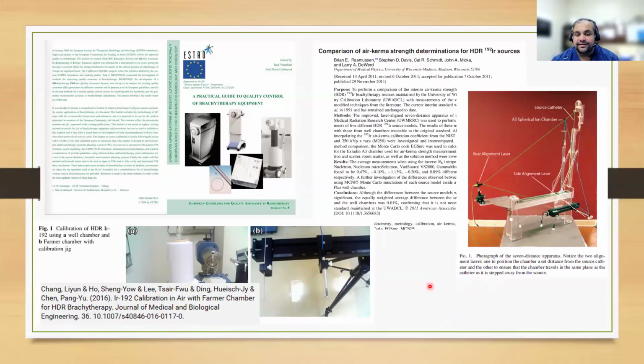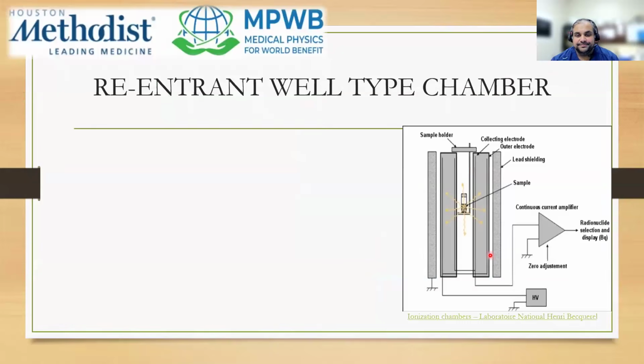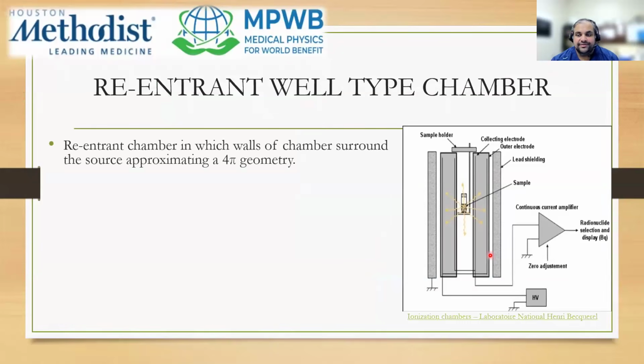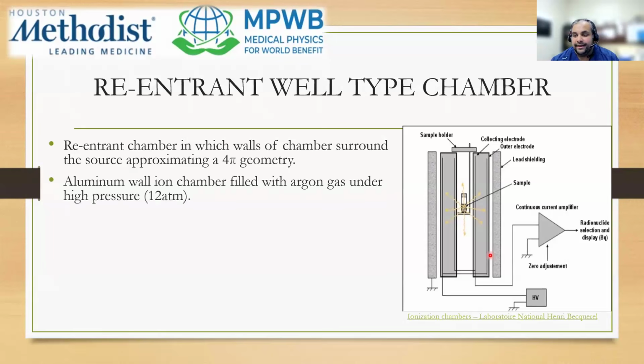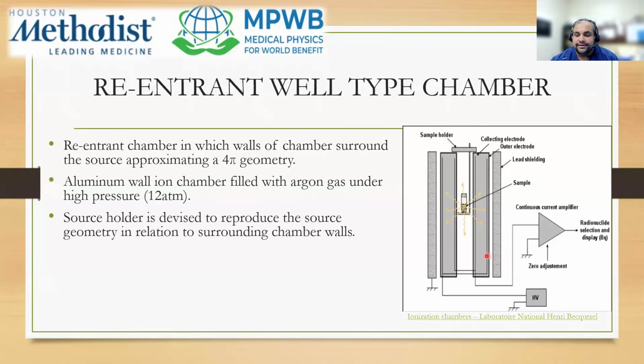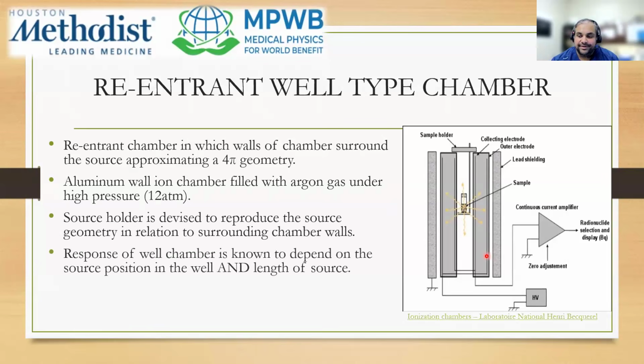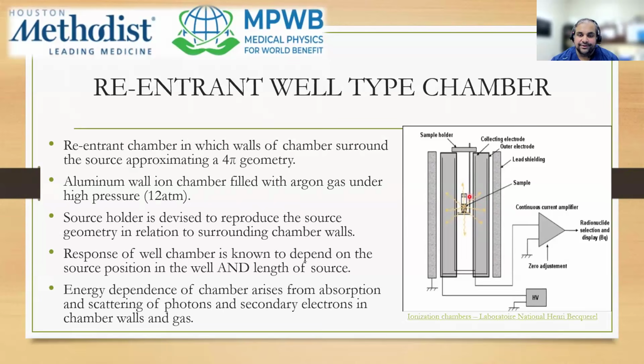Of course, the ESTRO document is here, where if you do not have the well chamber, I would highly recommend going through these two documents for the whole setup and how to do your measurements. But for your well type chamber, it's typically a reentrant well type chamber that is almost approximating a 4-pi geometry. And it's typically aluminum walled, argon filled, and pressurized to improve ionization efficiency and signal stability. Their response depends strongly on source position, source length, and the photon energy. Typically you'll find this well chamber in clinics that do brachytherapy.